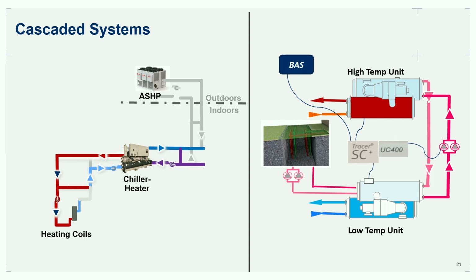That's awesome. It's also a really expensive, inefficient way to do that. Instead, what we want to talk about is splitting that lift between 2 pieces of equipment. So on the air source side, rather than trying to do 180 degrees of lift or whatever out of that air-to-water heat pump, let's deliver 60 degree water out of that. That's going to increase the COP on that air-to-water heat pump, which is your most expensive, least efficient piece of equipment in the system, dramatically.